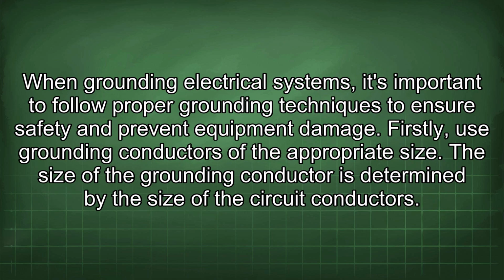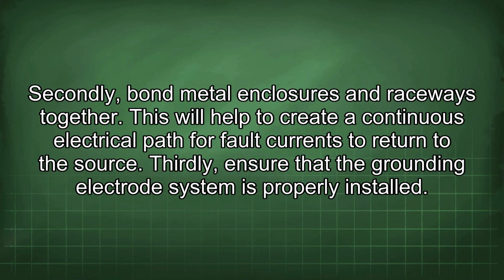When grounding electrical systems, it's important to follow proper grounding techniques to ensure safety and prevent equipment damage. Firstly, use grounding conductors of the appropriate size. The size of the grounding conductor is determined by the size of the circuit conductors. Secondly, bond metal enclosures and raceways together. This will help to create a continuous electrical path for fault currents to return to the source. Thirdly, ensure that the grounding electrode system is properly installed.